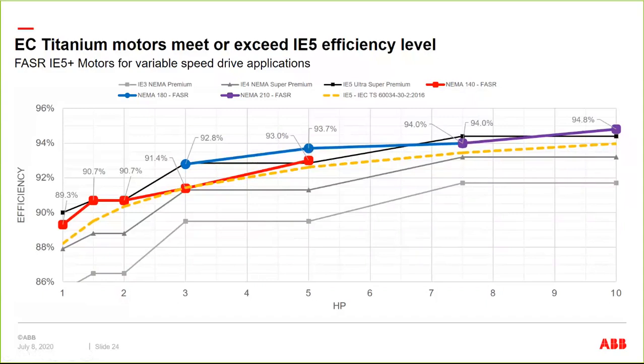So it's 0.7% higher than the IE5 standard. So even when you add a drive, in a lot of cases, it's still above IE5 standards. Now, again, remember I talked about power density. So you can get a 5 horsepower in a 180 frame, or you can get a 5 horsepower in a 140 frame. So you pay a little bit in efficiency, 0.7%, but it's still above IE5.